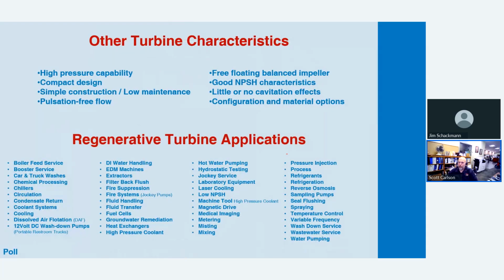Some of the other pump characteristics, besides the high pressure, are that they have a compact design. They're usually only a couple of parts: motor bracket, impeller, and casing, as well as the motor, seals and hardware. So there's not a lot of difficulty in working on them. They are a pulsation-free flow. If you compare that to a diaphragm pump or a piston pump that you would use for high pressure, those both have pulsation to them. Part of the reason for that is it is a free-floating, balanced impeller, so we don't fasten the impeller to the shaft. It works itself through the whole time.